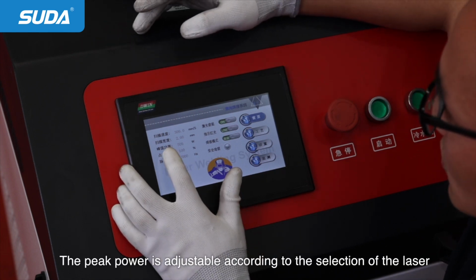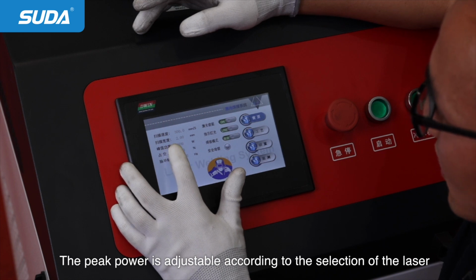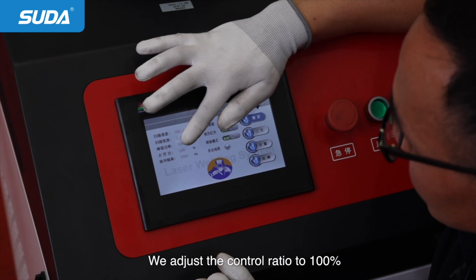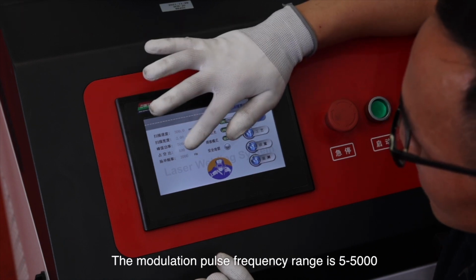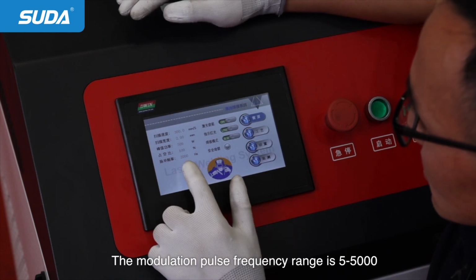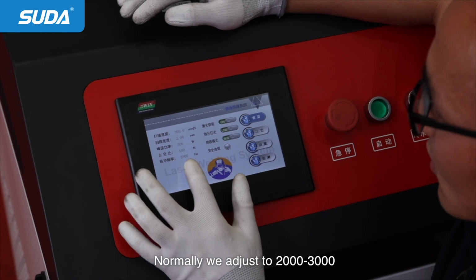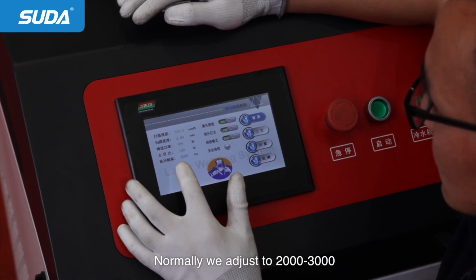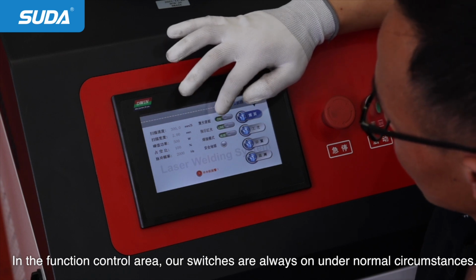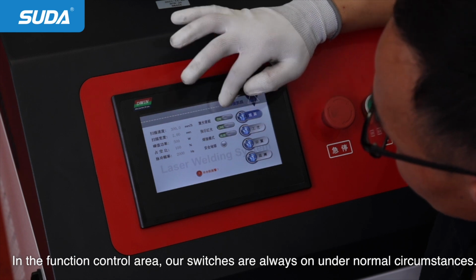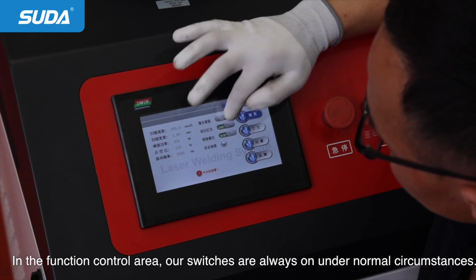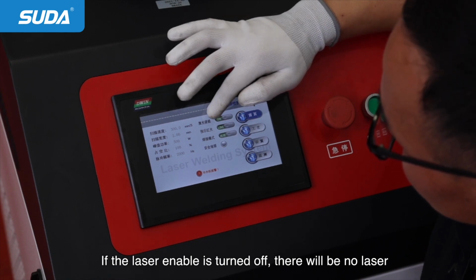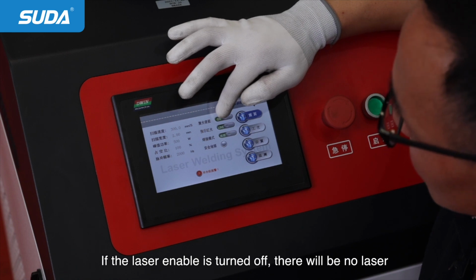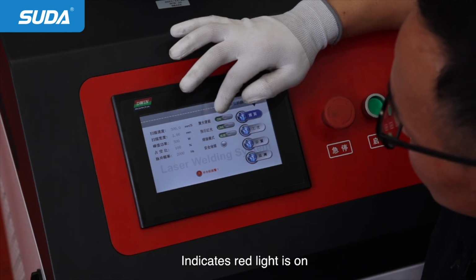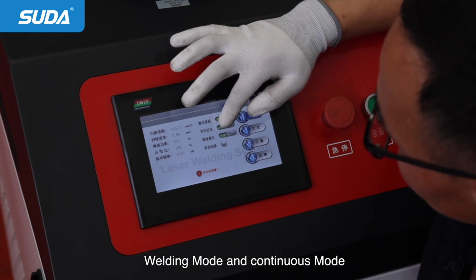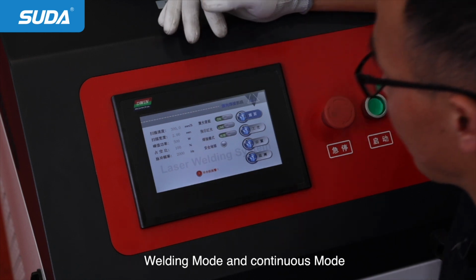The peak power is adjustable according to the selection of the laser. We adjust the control ratio to 100%. The modulation pulse frequency range is 5 to 5,000. Normally, we adjust to 2 to 3,000. In the function control area, our switches are always on under normal circumstances. If the laser enable is turned off, there will be no laser. Indicates red light is on. Welding mode and continuous mode.